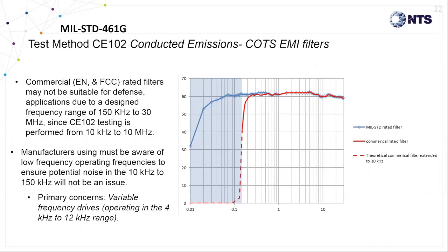Now, regarding filters, it's important to note that with an EMI power line filter, you must pay close attention to the design cutoff frequency. This is specifically important when commercial off-the-shelf equipment, known as COTS, is integrated into a subsystem. These devices are designed for commercial applications such as a home, office, or light industrial environment, and as discussed earlier, vary significantly from a military platform environment.